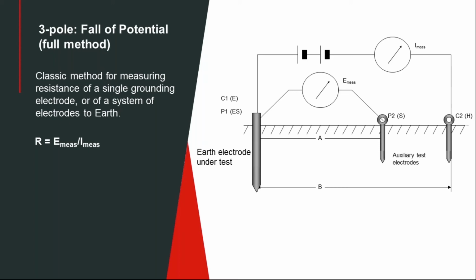So now in a resistance test, you're going to connect your tester to your ground, of course, and then you're going to run a current probe out generally as far as you can conveniently get it. The idea is you want it to be out of your way, and we'll show you why in a couple of slides. Then your potential probe, you're going to move that in intervals out towards the direction of your current probe, and you're going to take a series of readings. It's going to measure the resistance of A on this diagram. What is the resistance to the place you put your potential probe, excuse me. And I think on the next slide, if we can show that.